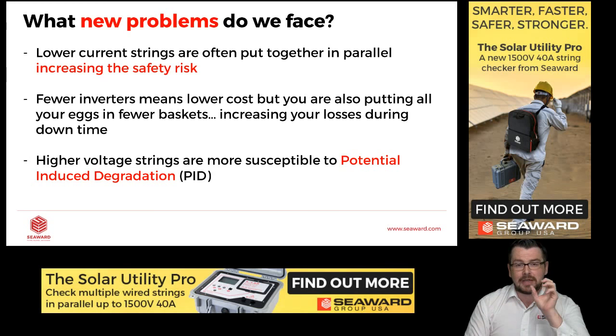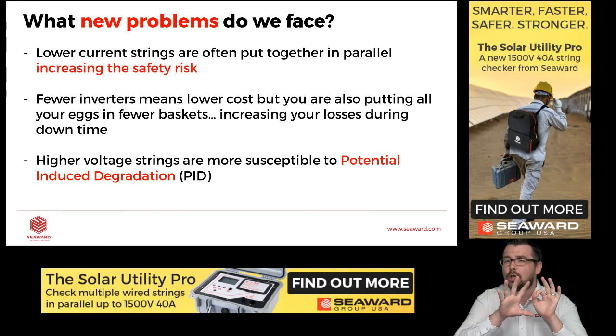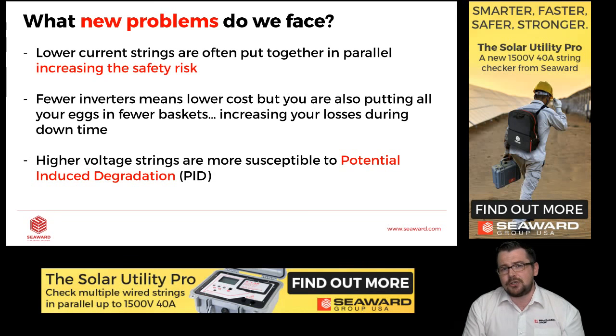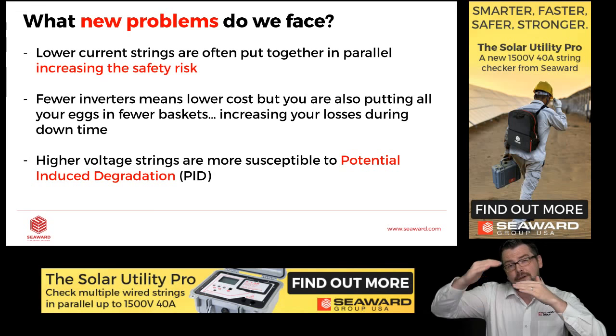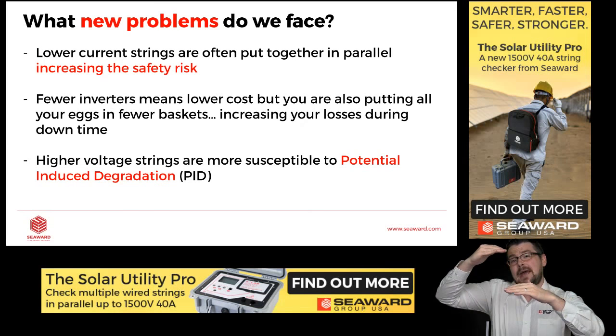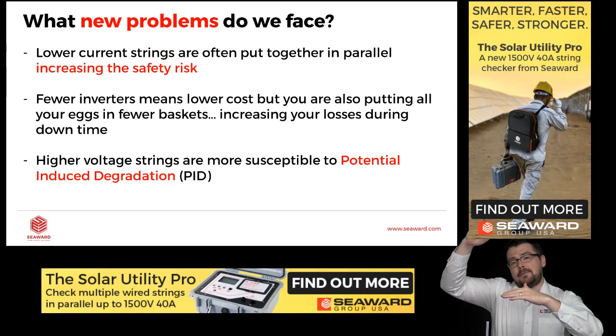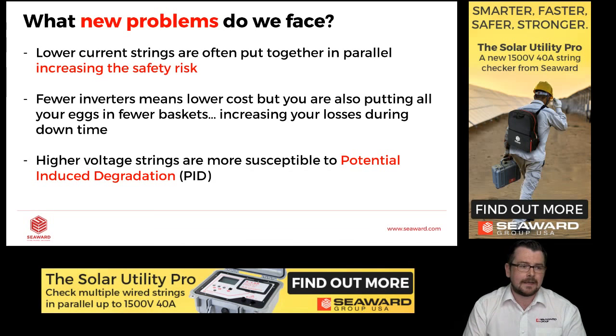Now, this means we can buy fewer fuses. All right, they're bigger, but we have to buy fewer of them. And also we have fewer combiner boxes again. But what that means is in that single fuse, there could be a lot more current than you're ever used to. So this is why with the Solar Utility Pro, we went for a really high rating of 40 amps. So we're at 1500V, 40 amps. So you're in a very good position where you've got a lot of headroom that if you test a 30 amp fuse, you've still got a lot of capacity there within the instrument.